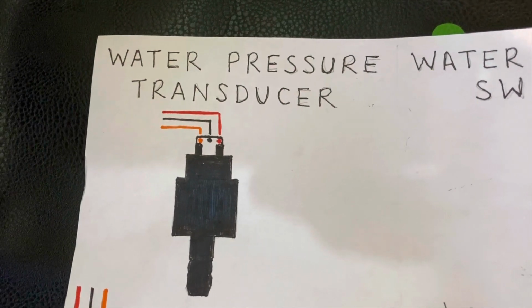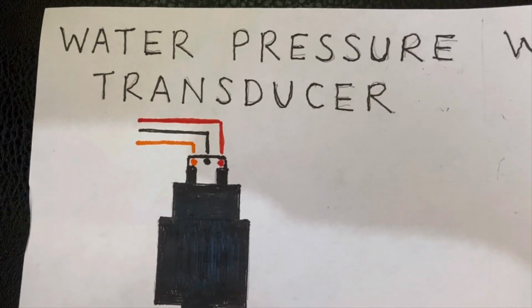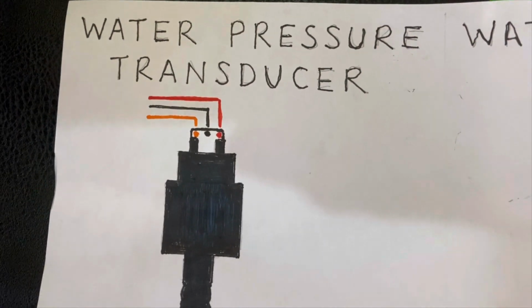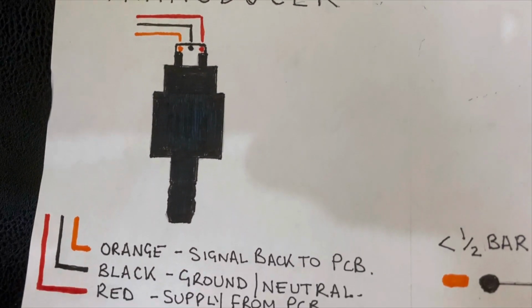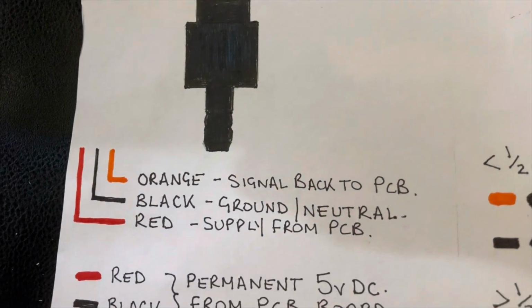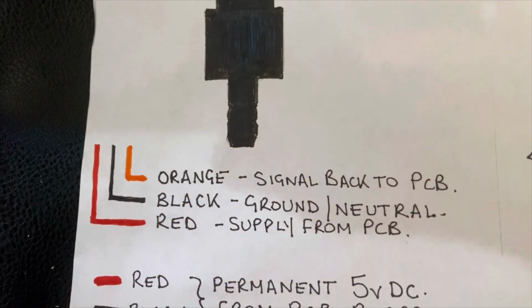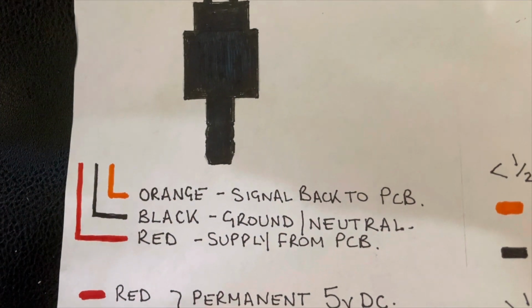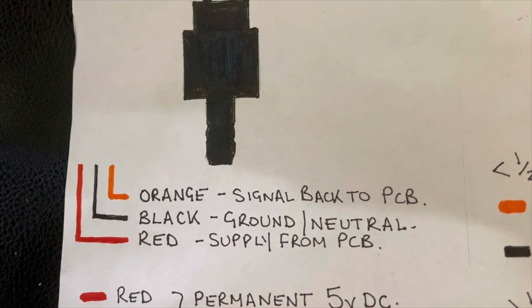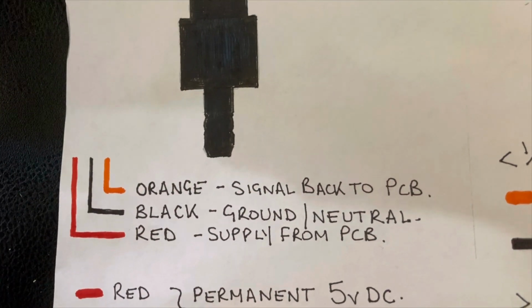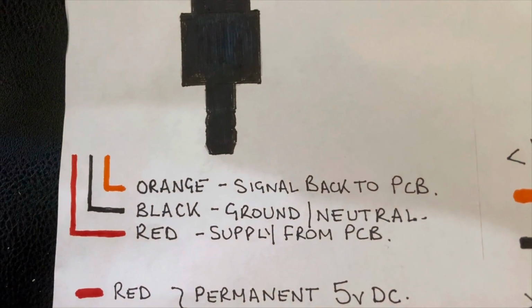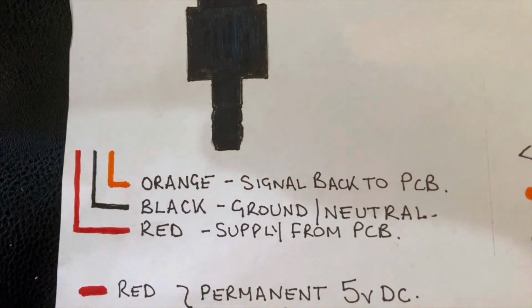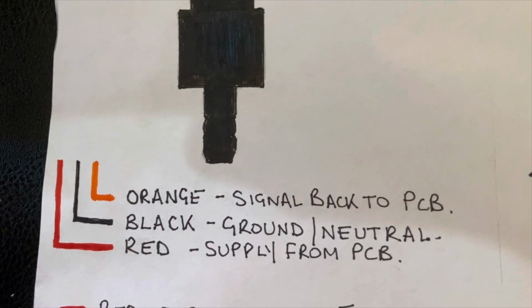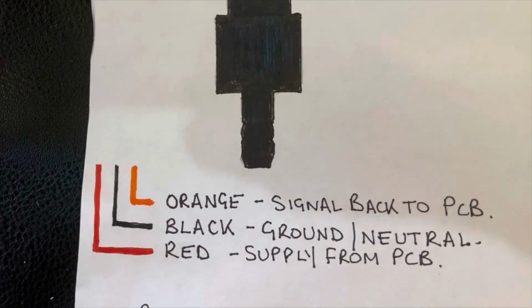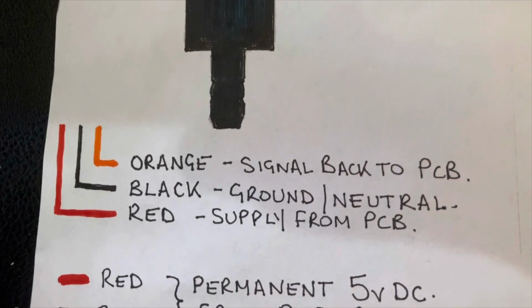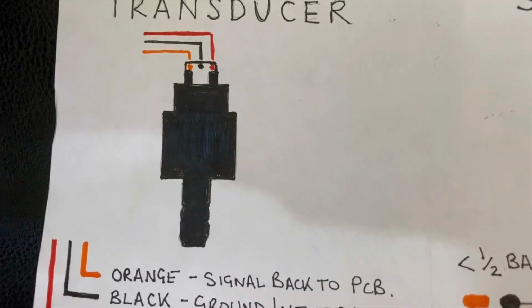So we'll look at the transducer first. This is the picture of the water transducer. We've got 3 cables. They're on the low voltage side of the circuit board, so you'll have to trace the cables. You can tell the difference between high voltage and low voltage side of the circuit board, generally because the high voltage side will have larger connections and larger diameter cable harness. On the low voltage side you'll see smaller connections and the thinner harness cables.